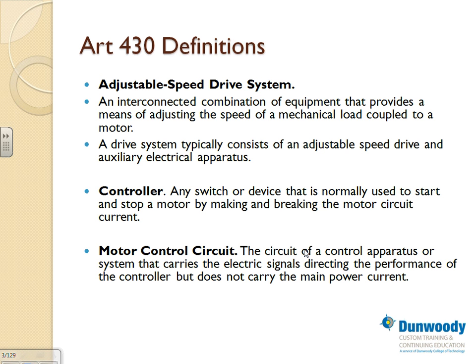VFDs, as you know, putting my engineering hat on, the only time we specify a VFD on a motor is if you need speed control. That's the main part. You don't want to put a VFD on any motor if you don't need to control its speed. With speed control you can ramp up your motor, so that is a soft start on your mechanical equipment and on the grid, right? With a soft start, there's no impact on the power distribution system in your building. Ramp it up, come up to speed, and when it shuts down you can ramp it down, so that also has less impact on your mechanical and electrical equipment. So that's ramp up, ramp down. A soft start can do that. A VFD, of course, does much more than that.